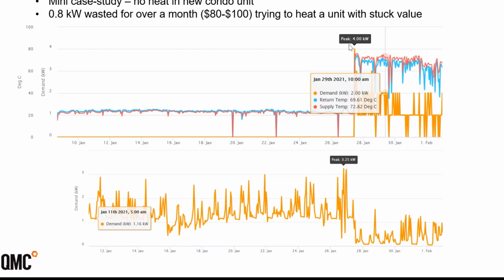It wasn't opening and closing. That was the reason the supply and return temperature were very close within that unit, and the electricity consumption within the same period was spiking and going up.